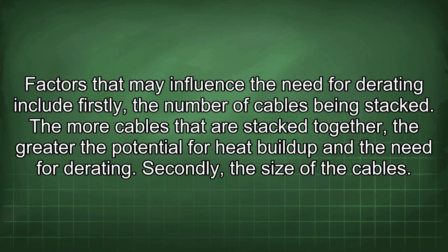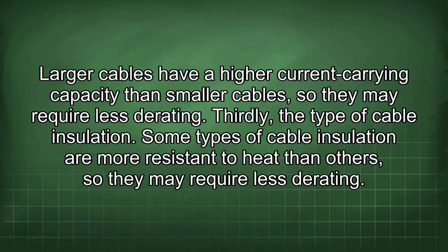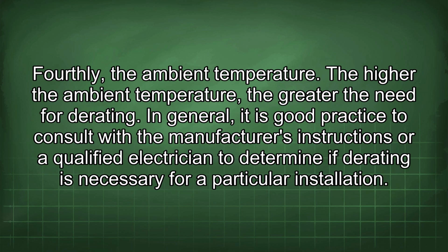Factors that may influence the need for derating include, firstly, the number of cables being stacked. The more cables that are stacked together, the greater the potential for heat buildup and the need for derating. Secondly, the size of the cables. Larger cables have a higher current carrying capacity than smaller cables, so they may require less derating. Thirdly, the type of cable insulation. Some types of cable insulation are more resistant to heat than others, so they may require less derating. Fourthly, the ambient temperature. The higher the ambient temperature, the greater the need for derating. In general, it is good practice to consult with the manufacturer's instructions or a qualified electrician to determine if derating is necessary for a particular installation.